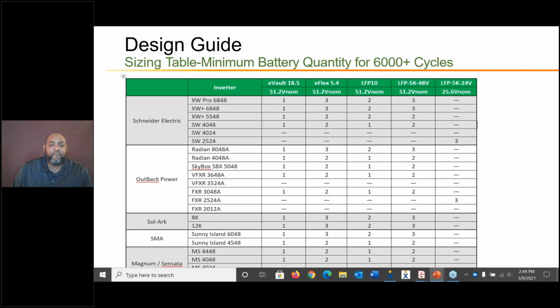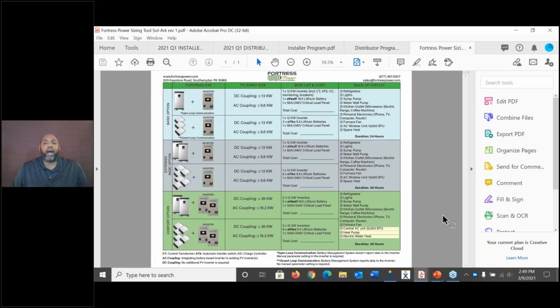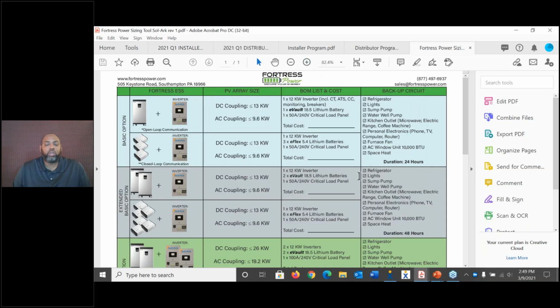When we do the mathematics here, you will notice that you will see an eVault battery, and I'm just using the Sol-Ark one as an example, 1 eVault to 1 Sol-Ark. If you want to have the eFlex unit, you would need 3 of these batteries per eFlex. So we designed a chart that I don't know how many people we have shared this with, but I want to show you this. This is just an example of how you could size a system for a user. This is an example of a basic option. If I wanted to size a system for a homeowner, what is needed? So we look at the Fortress battery offering with 1 Sol-Ark. If we go to this bill of material list in the middle, you can see that 1 12 kW inverter is giving you 50 amps of critical load. These are the types of loads that you could back up with 1 inverter.